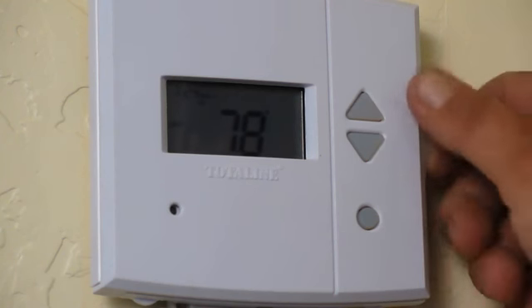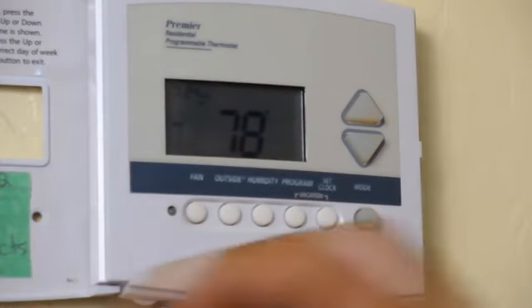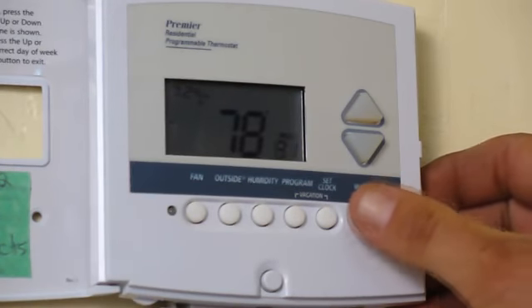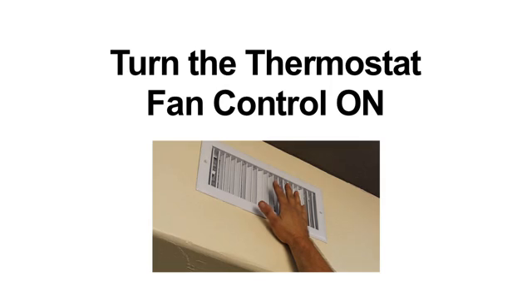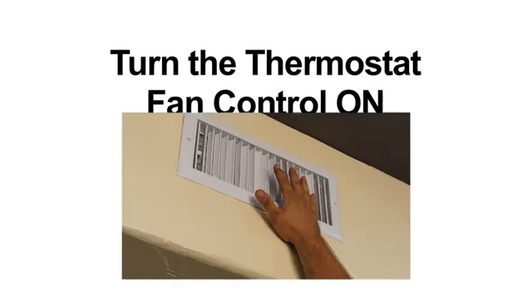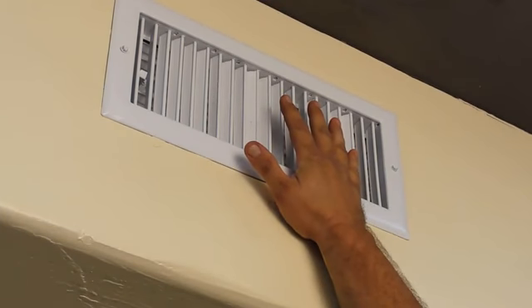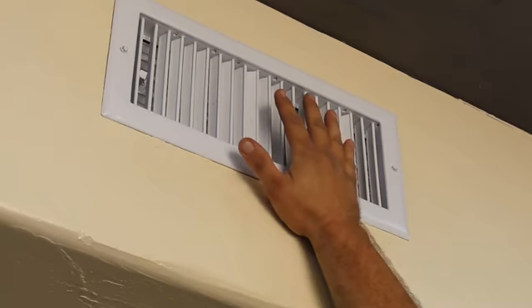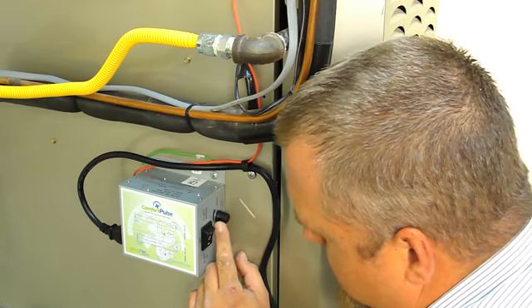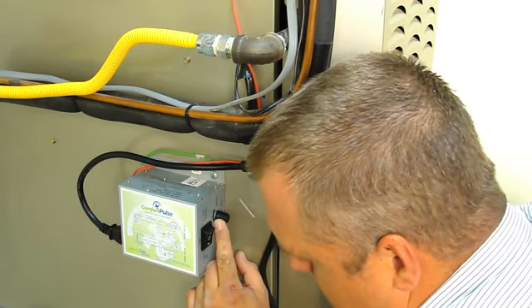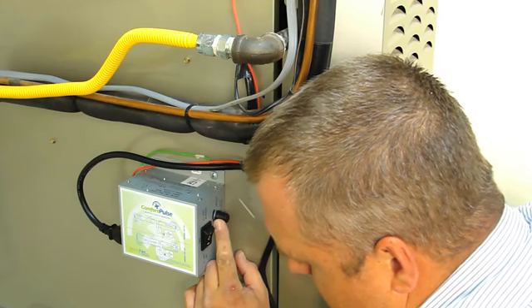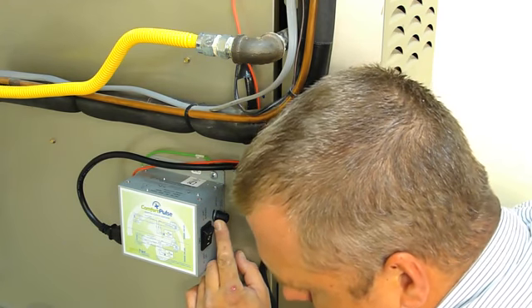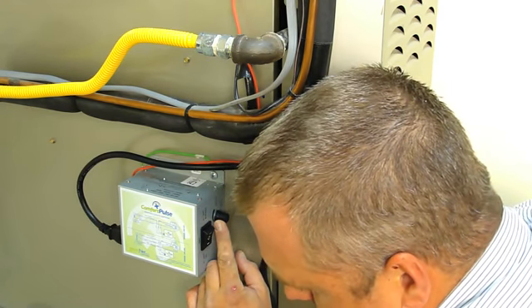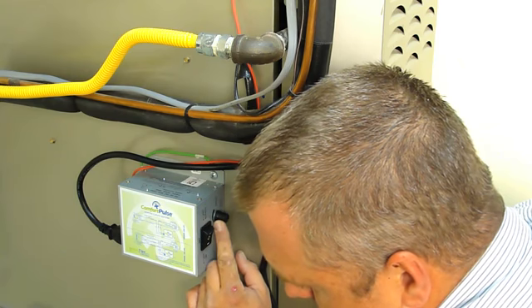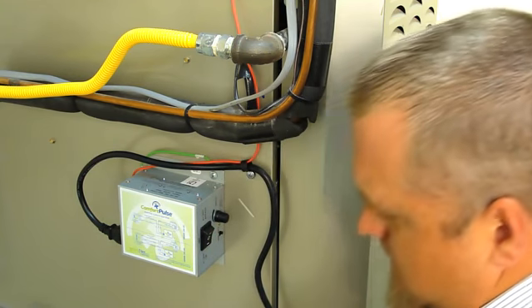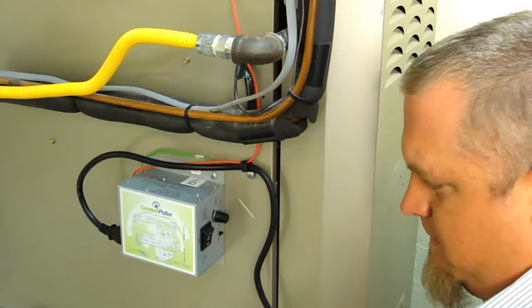First, turn the AC system on auto or cool. Turn the thermostat fan control on. Verify the air handling unit fan starts to idle speed. Set it high enough using the speed knob on the Comfort Pulse for the motor to idle properly. Listen to see if there are any abnormal variations or whether the fan resonates, and adjust the speed knob on the Comfort Pulse clockwise until the motor vibrations or noise stop.